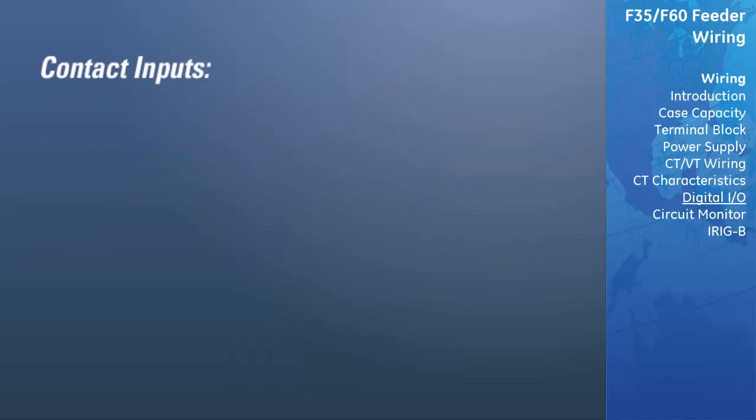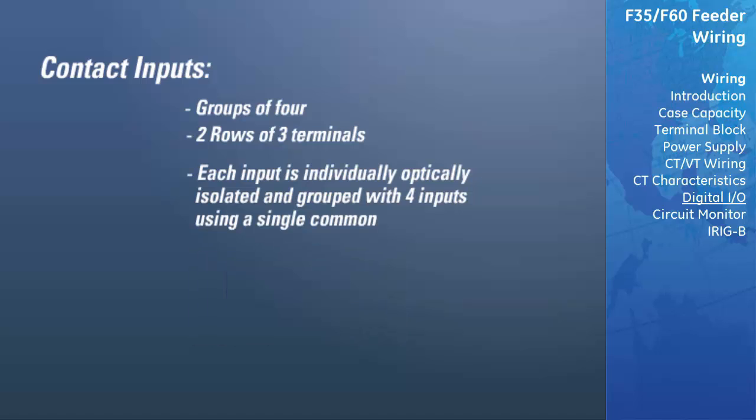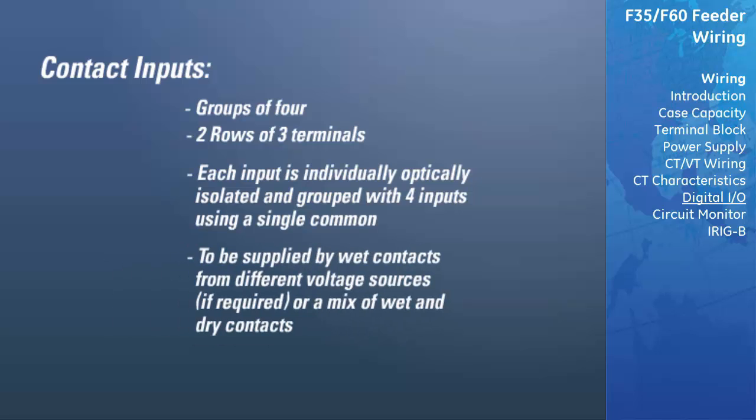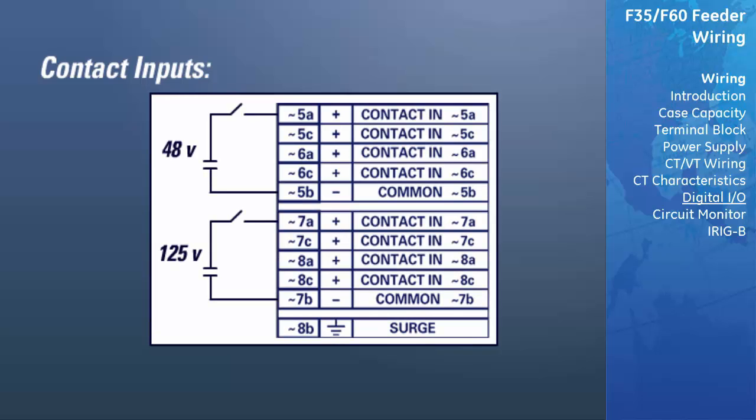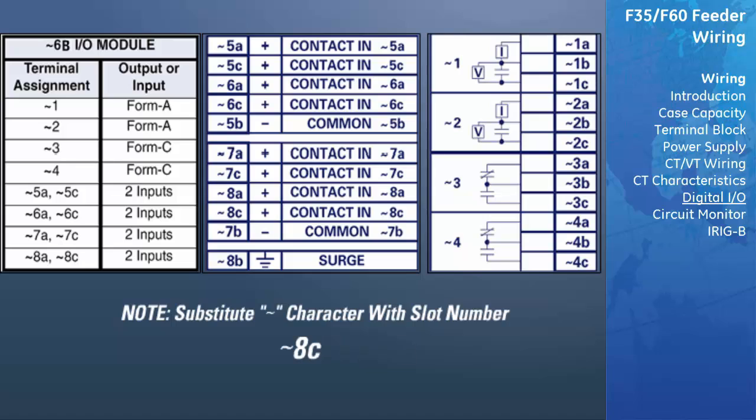Contact inputs are arranged in groups of four and use two rows of three terminals. Each input is individually optically isolated and grouped with four inputs using a single common. This allows each group of four inputs to be supplied by wet contacts from different voltage sources if required, or a mix of wet and dry contacts. The table shown illustrates the 6B module and contact arrangement. Since an entire row is used for a single contact output, the name is assigned using the module slot position and row number. Since there are two contact inputs per row, these names are assigned by module slot position, row number, and column position.